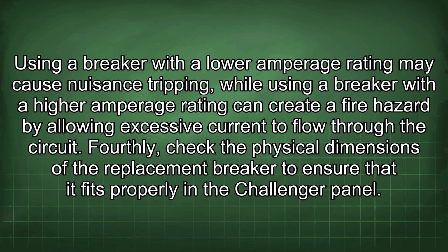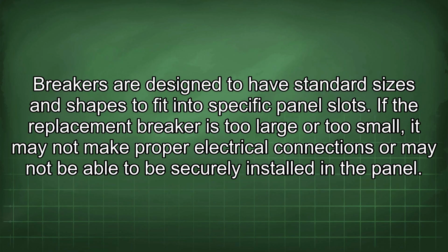Fourthly, check the physical dimensions of the replacement breaker to ensure that it fits properly in the Challenger panel. Breakers are designed to have standard sizes and shapes to fit into specific panel slots. If the replacement breaker is too large or too small, it may not make proper electrical connections or may not be able to be securely installed in the panel.